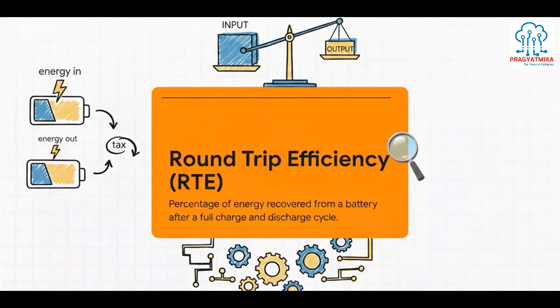This brings us to a crucial metric, round-trip efficiency, or RTE. Simply put, RTE measures how much energy a battery returns compared to the total energy you used to charge it in the first place. If you buy 100 megawatt hours of power from the grid and put it into your battery, you are never going to get 100 megawatt hours back out. The laws of physics essentially demand a tax on that transaction.